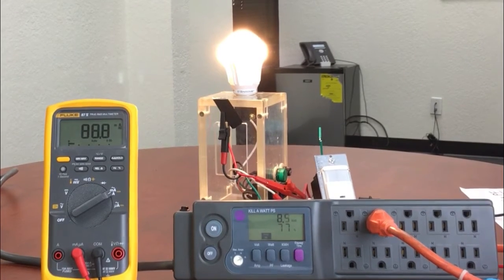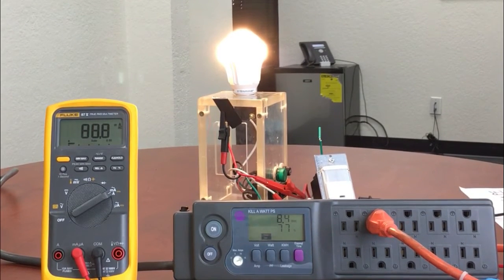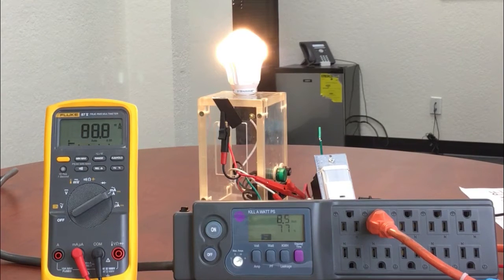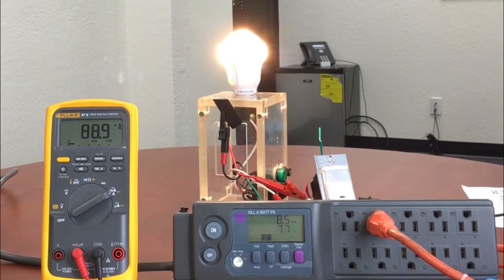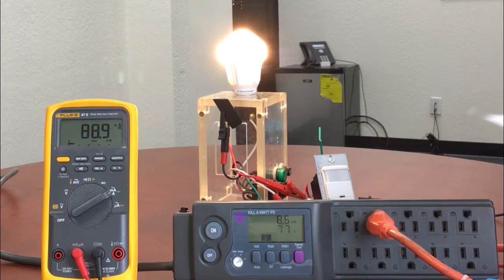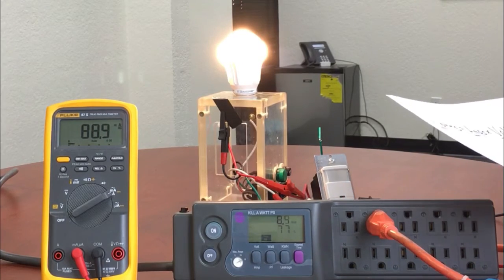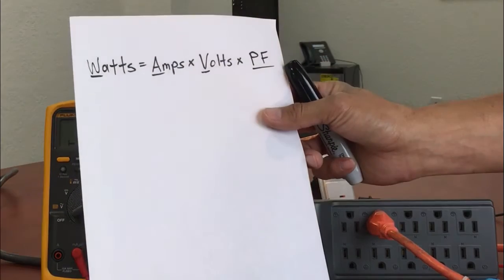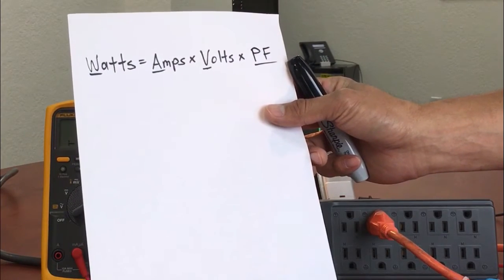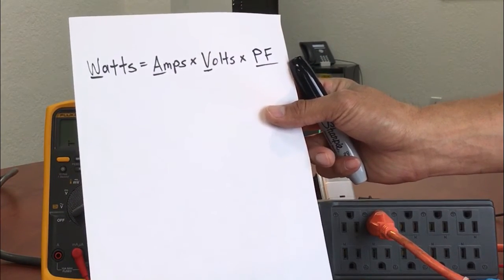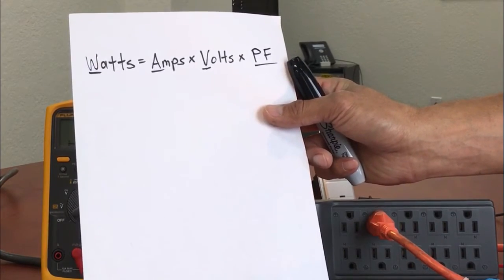Now let's put all the numbers together and calculate the amount of energy being used. Let's start first with a formula that will give us wattage when measuring AC, and that formula is watts equals amps times volts times power factor.